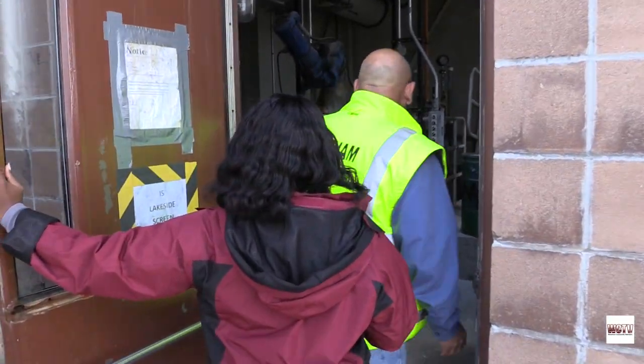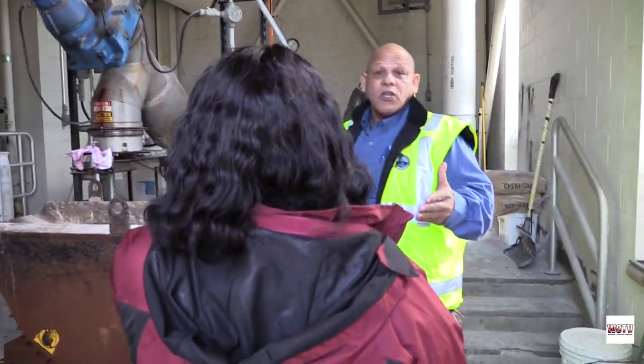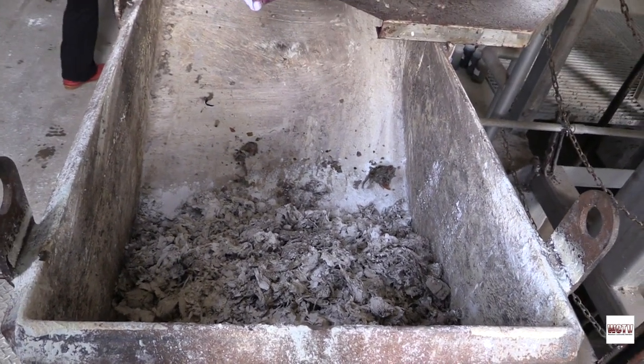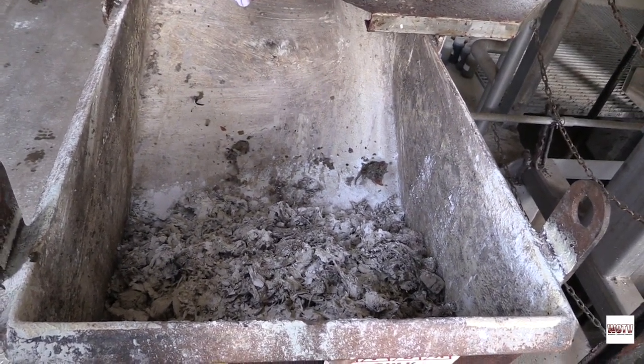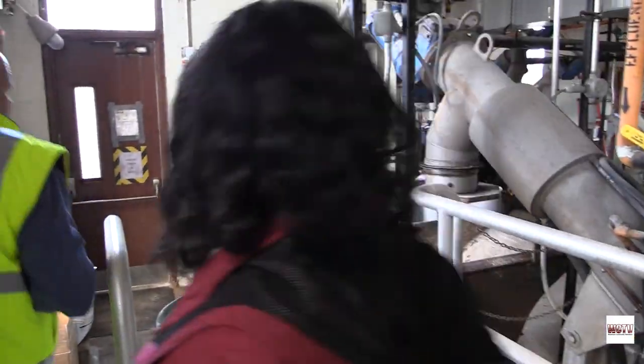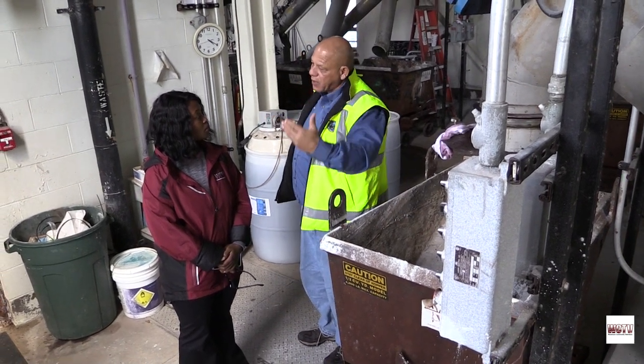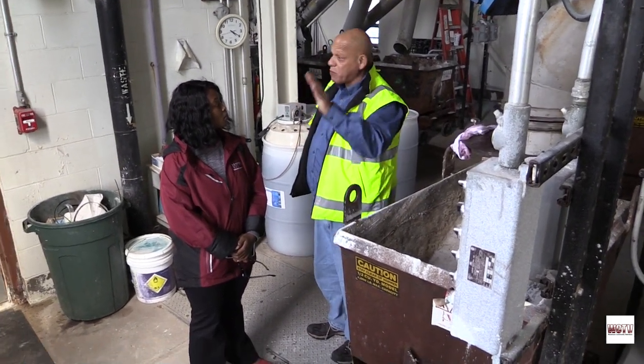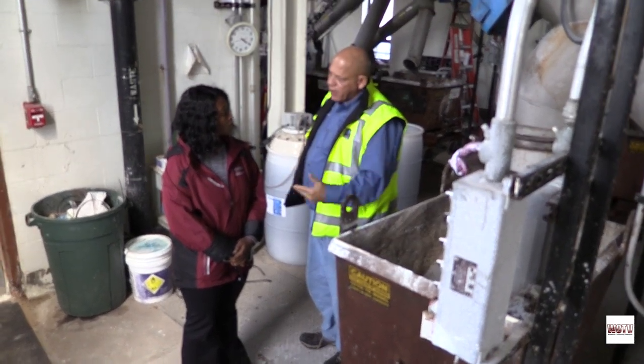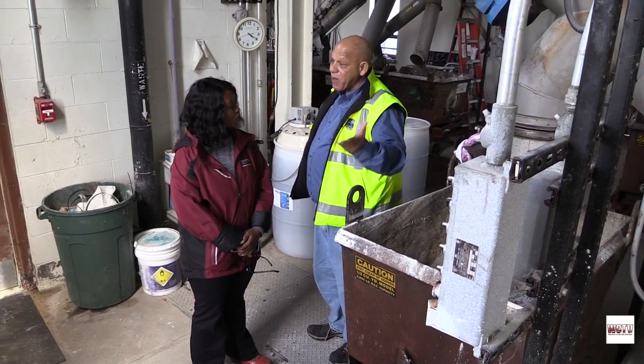The first phase, also known as the primary phase, is where non-biodegradable materials are separated from the wastewater. Each day, about a bucket worth of these materials are pulled. This not only exhausts manual labor, but is also detrimental to the machines. Each pump cannot handle these. So we're constantly taking the pumps out, taking the rags out, and putting the pumps back online. If we don't do that, the pumps won't work, and then the level will rise in that wet well and back up into folks' basements. So people have to be dispatched immediately.